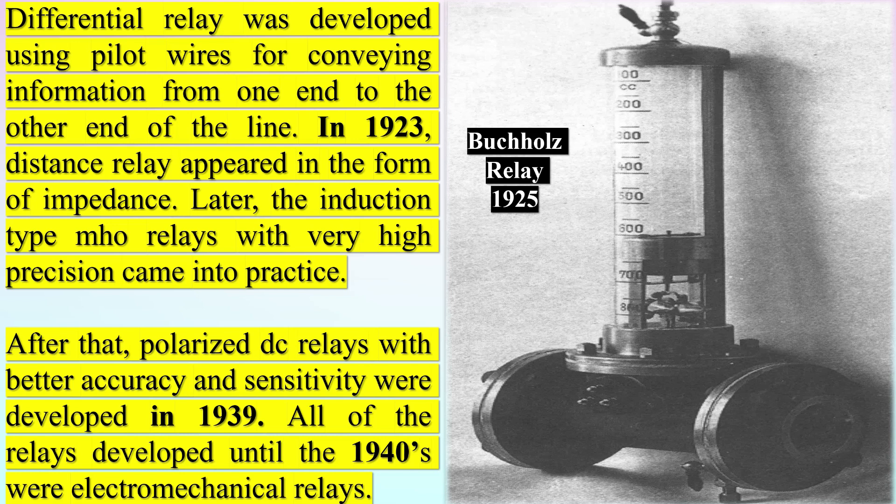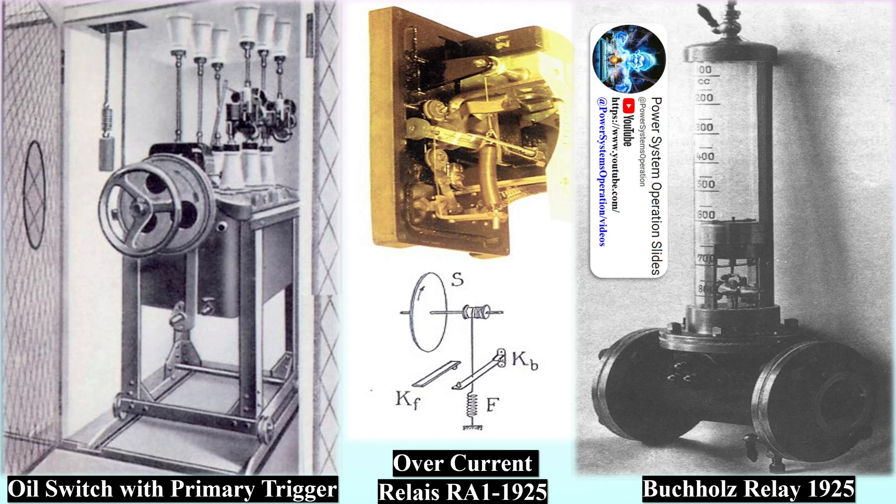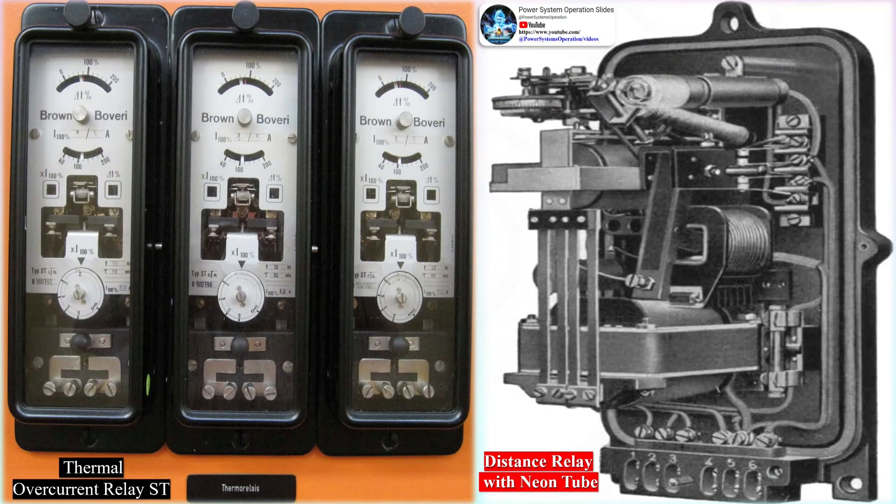All relays developed until the 1940s were electromechanical relays. These devices achieved very high precision and sensitivity in the form of induction cup mho relays and performed well for their missions. The early 1940s showed the way into the development of relays using electronic devices, known as static or solid-state relays because they contained no moving parts. The advent of transistor circuits opened the door to new protection concepts like block spike comparator and phase comparator. The major advantages were no moving parts, higher operating speeds, faster reset times than electromechanical counterparts, and more precise settings. This generation of static relays became quickly very popular and found a large place in power system protection.